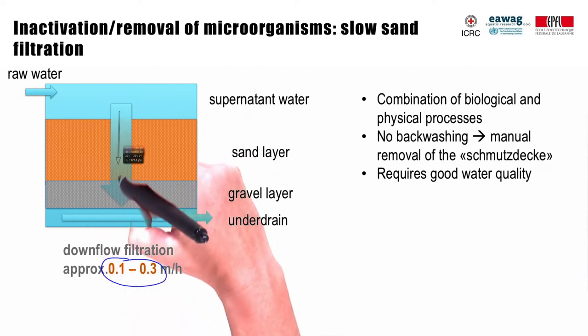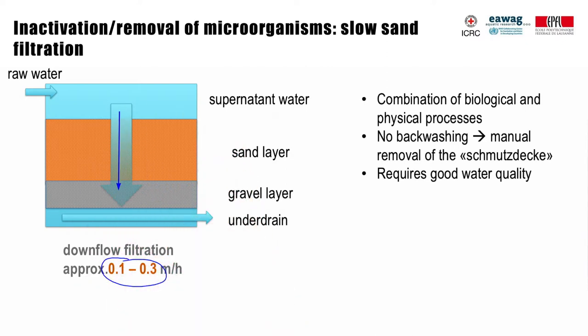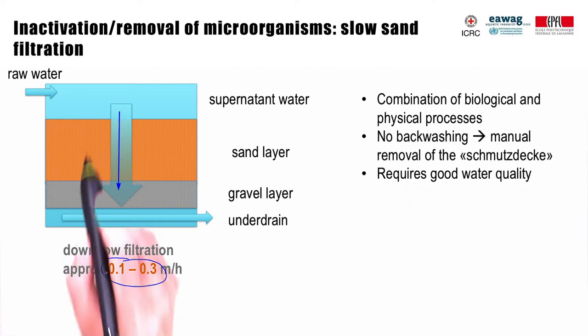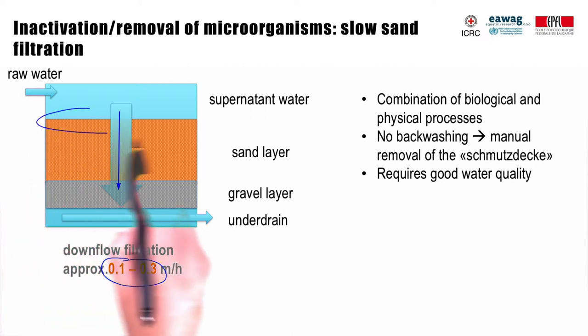Slow sand filters are usually downflow filters and are operated by gravity. Each filter requires a ripening period of a few days to a few weeks until removal rates stabilize. The top layer of the slow sand filter contains a diverse microbiological community and particles, and is called the schmutzdecke. In the schmutzdecke, inactivation of microorganisms predominantly occurs.